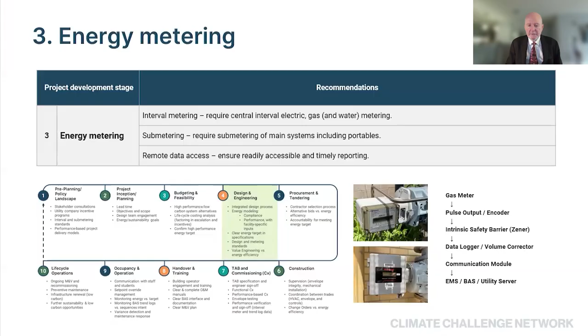So looking in this case, these are the kind of analytics you do with central electric interval metering and gas fuel interval metering. This is taking one of those schools and looking at it across the four seasons of the year. I'm not going to dwell on what this is all telling us, but by looking at different periods for the same school measured in kilowatts, you get such a good sense of where the operating efficiencies and inefficiencies are, and the opportunities. Looking at that base load in terms of electricity consumption, what makes that up? Why is that electricity use still happening in the middle of the night and on weekends? So interval metering is an amazing diagnostic tool, and a very practical one.